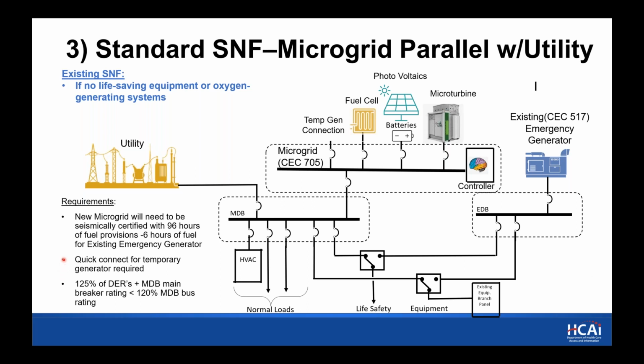And one thing I'll just point out, and this gets into the design, this is a 705 code, is this main distribution board, MDB, is going to need to be sized so that 125% of the distributed energy resources that are introduced plus the main breaker is less than 120% of this board. So essentially the 705 code says I have multiple sources. I need to make sure I'm not exceeding the rating of this board. And typically what we see is that the existing condition is the main distribution board, main breaker, and the main board are matched. I'll say, just for instance, a 600 amp breaker and a 600 amp board. But what we see is typically that the actual demand load on this board is lower. So what we've seen successful is this main breaker being downsized to allow you to add this microgrid and still work with the existing main distribution board.